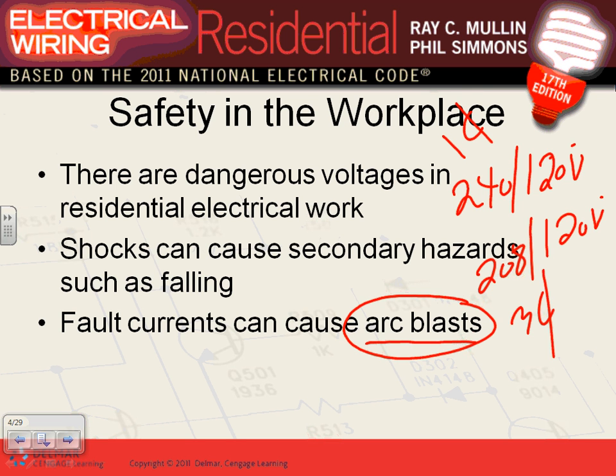These are the most common voltages you're going to use in residential. If you think you're going to use 480/277 in residential, you're probably wrong for the most part. This one is for single family dwellings and small apartment buildings, 240/120, very common. When you get into risers, 10-story buildings and so forth, you start moving into 208/120. More power, more juice.